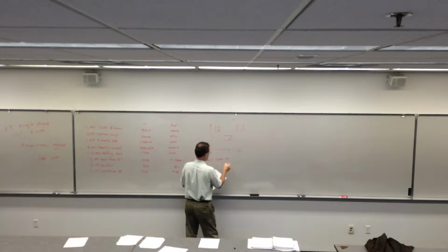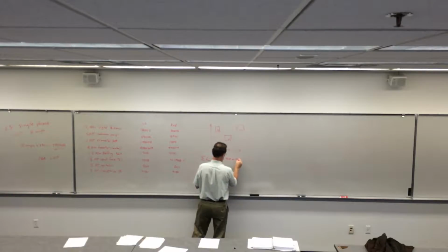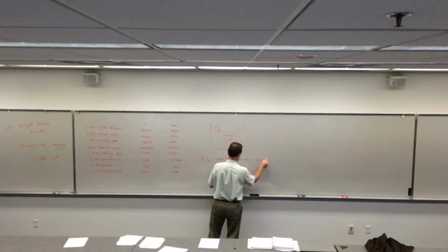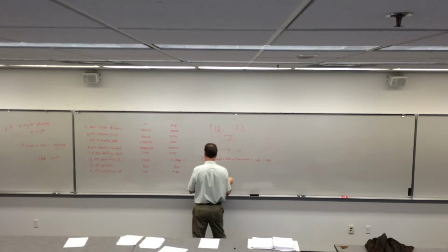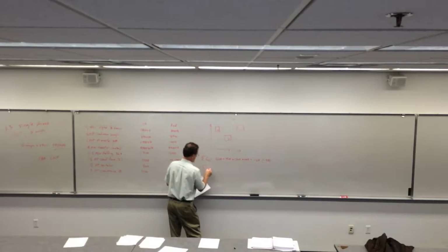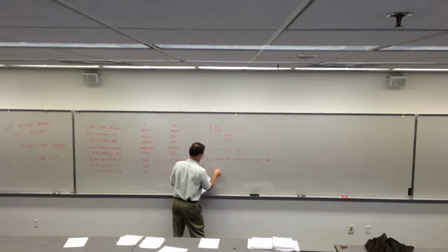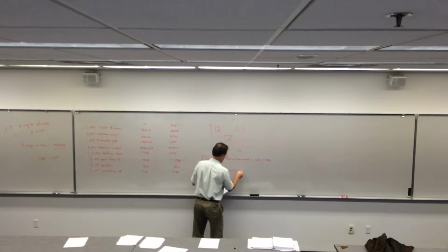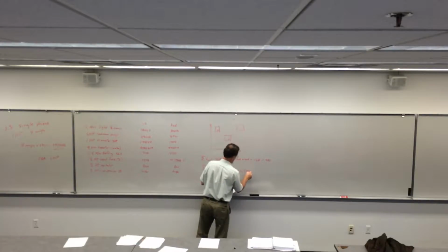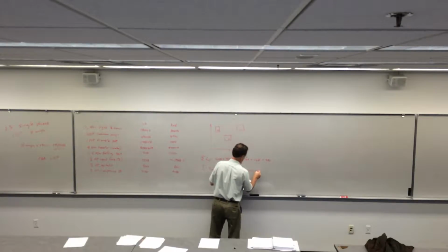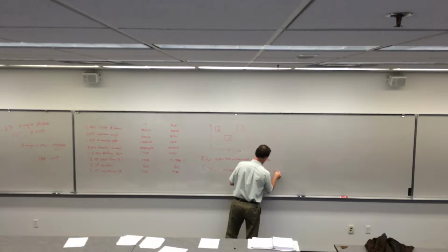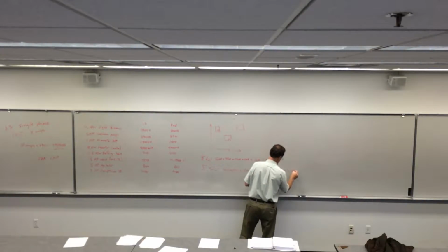75 amps, just some of the loads, 75 amps for the other, plus 120 amps, plus 160 amps, plus 15 amps. So you end up with 420 amps of the sum of the loads. Then if you do the sum of the X times L, you get 50 amps times 100 feet, plus 75 amps times 100 feet, plus 120 amps times 250 feet, plus 160 amps times 250 feet, plus 15 amps times 150 feet.